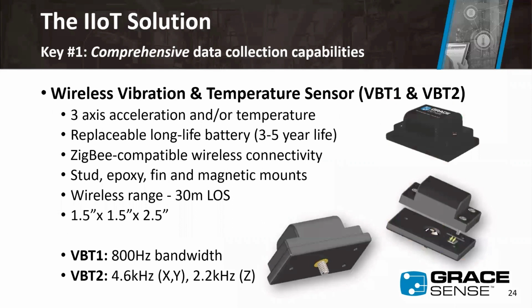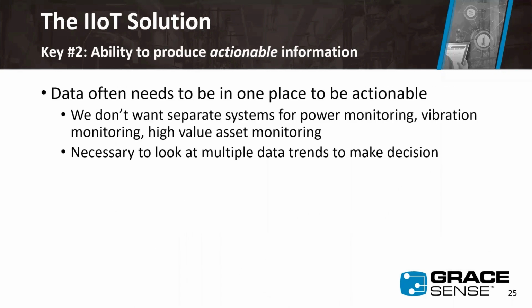The second targeted device in this line is our vibration and temperature node—triaxial accelerometers with a temperature sensor. They can be magnetically deployed or permanently affixed to a rotating asset like a motor, pump, compressor, or bearing, giving insight into what's happening inside that asset, ideally providing early indication of when it's starting to degrade or fail. I think I have a slide that dives into how we use that.